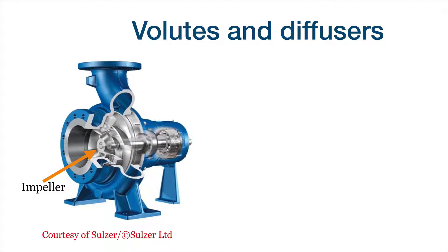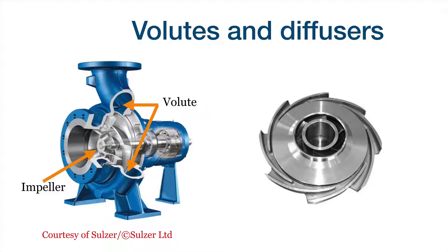We have already seen what a volute was. Here we will see another kind of device to transform velocity into pressure: diffusers. The volute has an area increasing in a spiral shape. The diffuser plays the same role as the volute — the area is increasing along the flow to transform velocity into pressure. Diffusers are normally used in multi-stage pumps, and the volute is normally used in single-stage pumps.